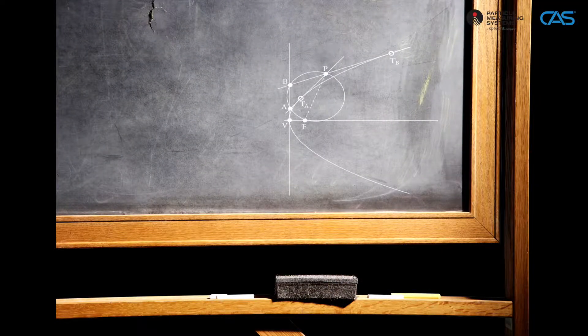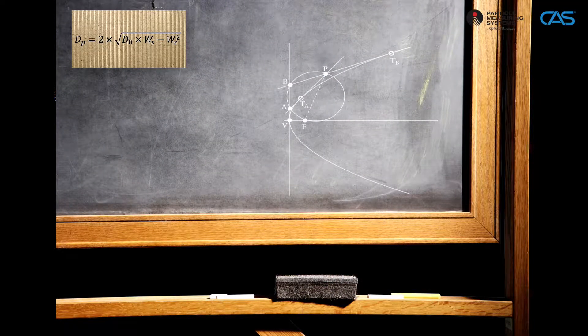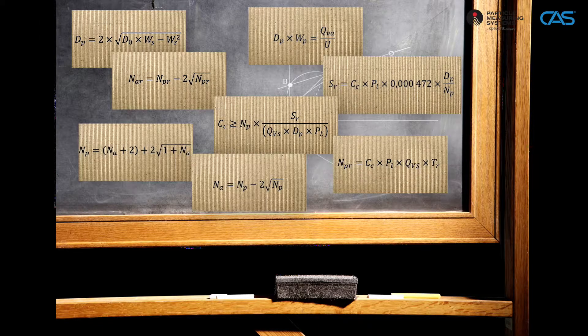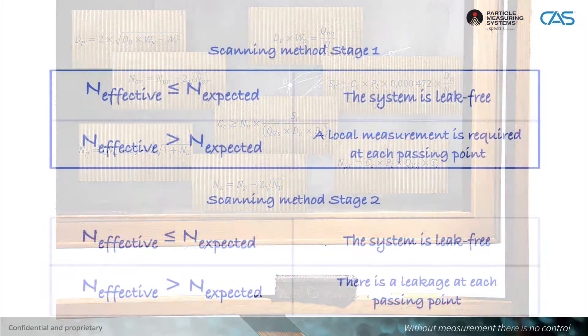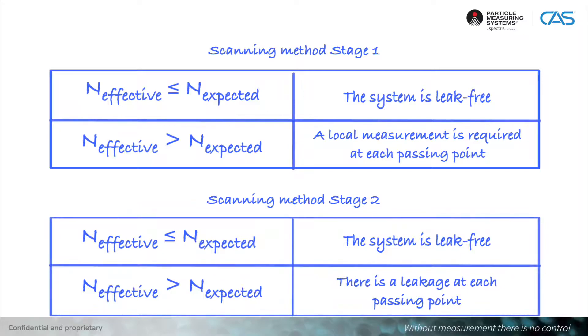Following the measurement, the expected amount of particles is determined based on complex calculations depending on the raw air and filter class. The evaluation then takes place as follows: the effective number of particles is compared with the expected number of particles. As long as the effective number of particles is less than or equal to the expected number, the system is leak-free.